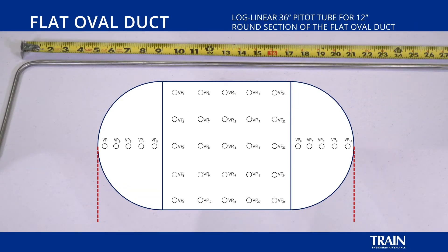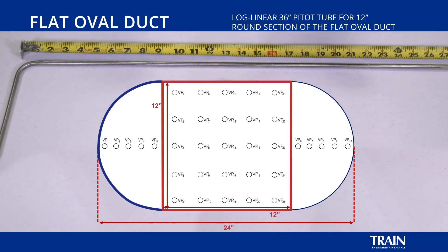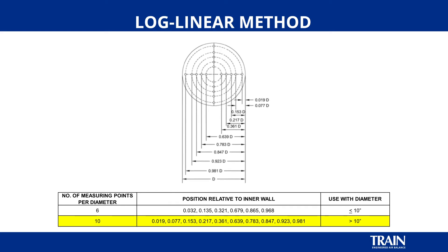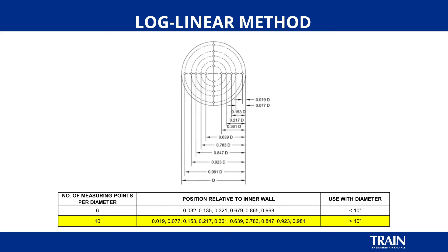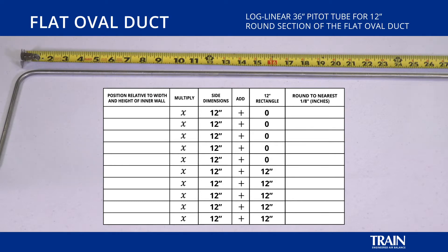Next, we will be performing the log linear portion of the flat oval traverse. This is a 24 inch wide by 12 inch tall flat oval duct, and we will be performing the log linear traverse from one side of the duct. We will need to make our markings for the circular portion of the duct on the first half of the pitot tube, and then account for the 12 inches of rectangular duct work, and then finish up with the last circular log linear measurements. In order to mark our pitot tube for this traverse, we will be using the log linear chart and method, which indicates ten factors to multiply by the diameter of the ductwork. The first factor for the log linear method for the 12 inch circular portion is 0.019, which results in one quarter inch on our pitot tube.